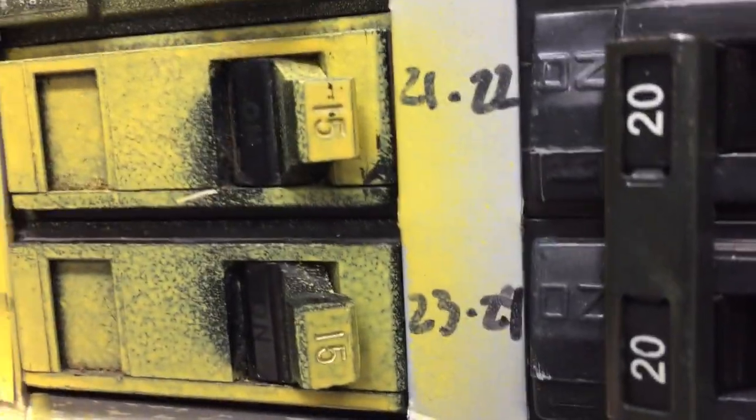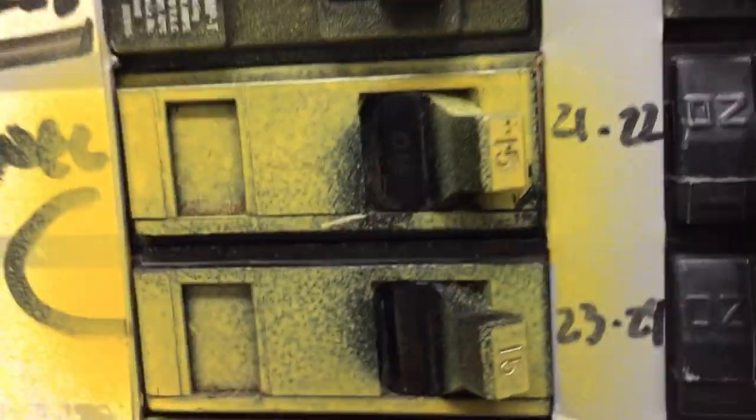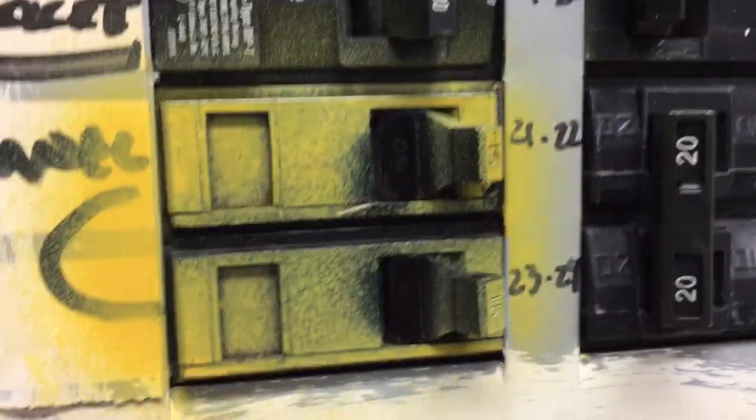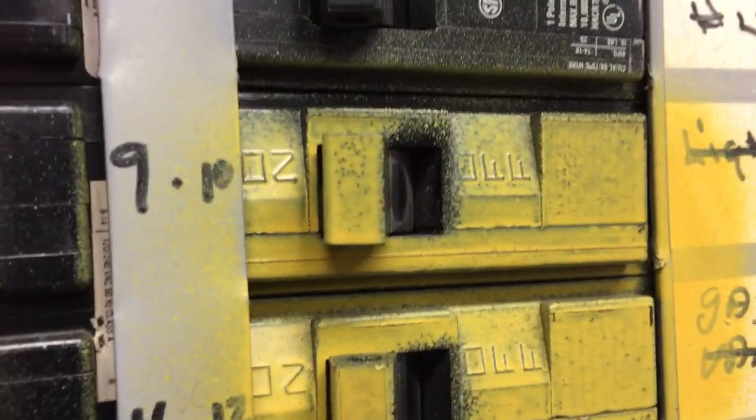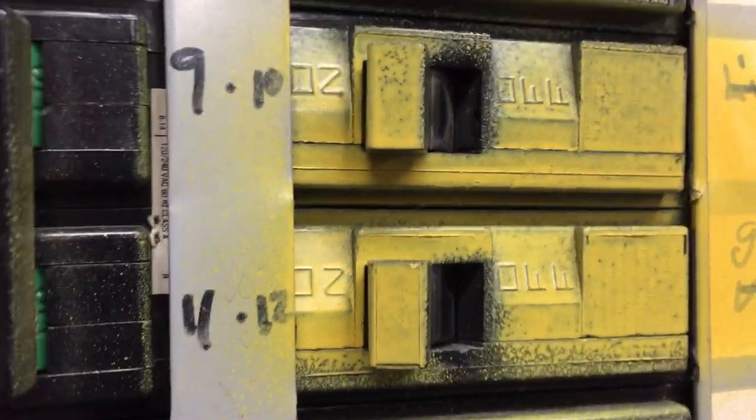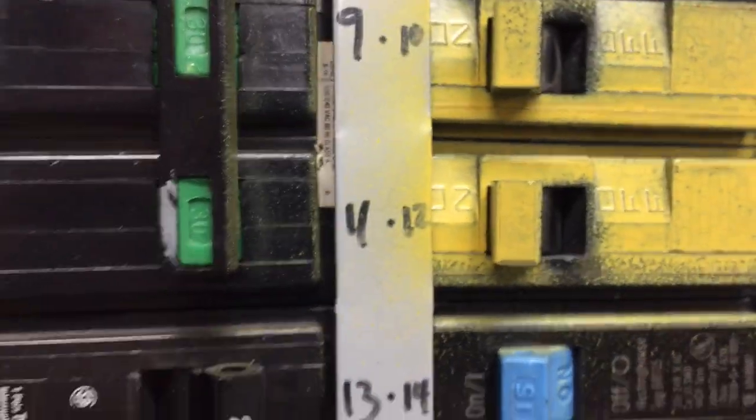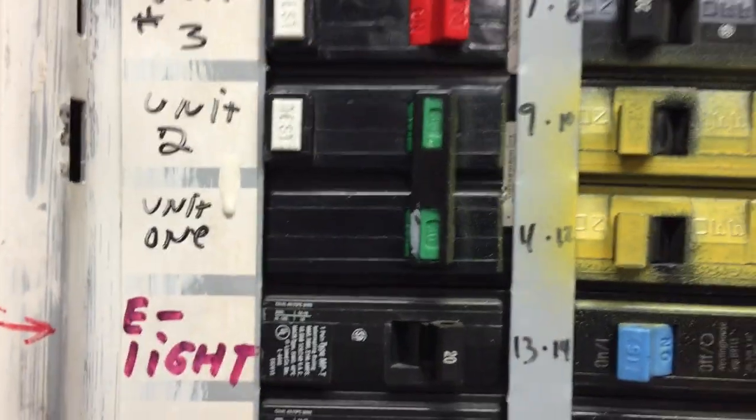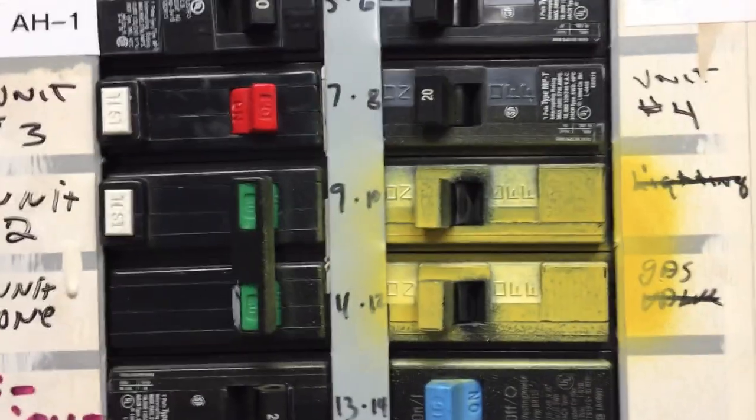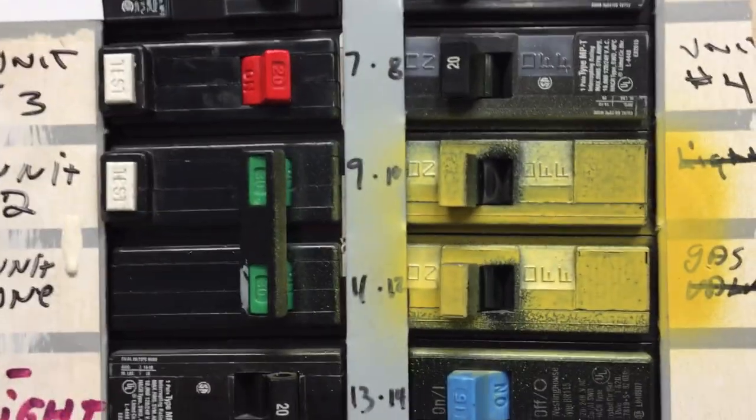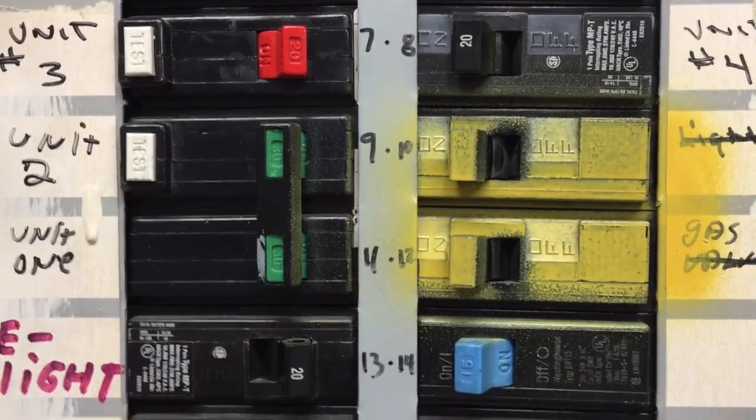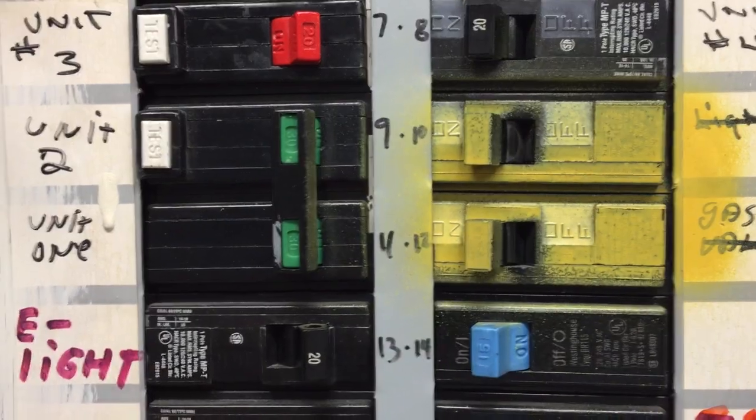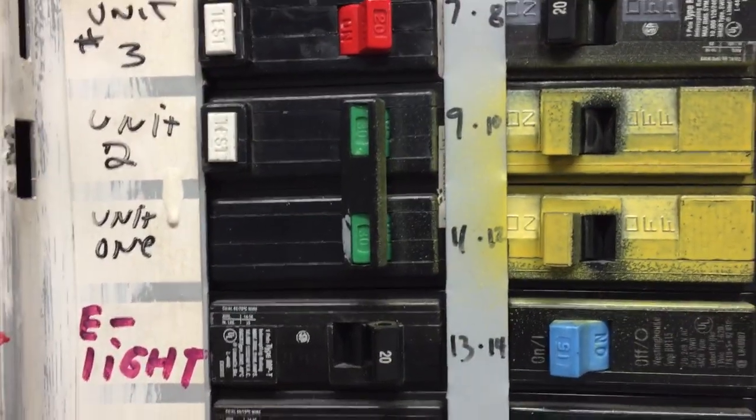Now this spray paint is certainly interfering with the markings required by 110.21A1 and also the markings required by 240.83A. We really can't tell the amp ratings of these circuit breakers here, the ones that are spray painted yellow, could be 15s or 20s, not sure. So that's a problem.